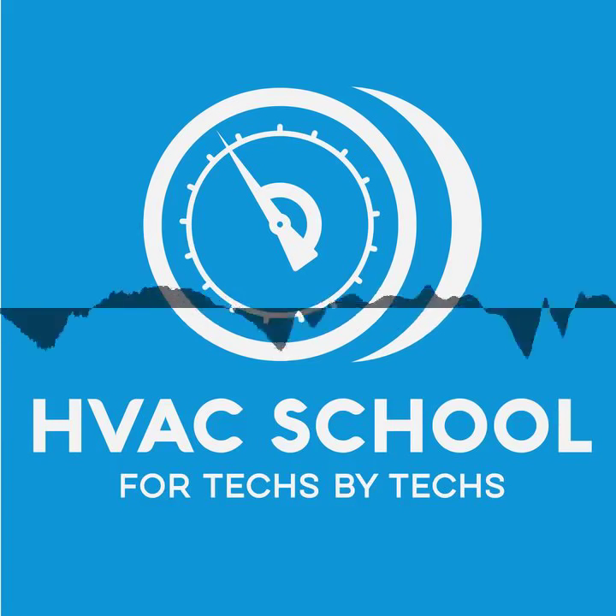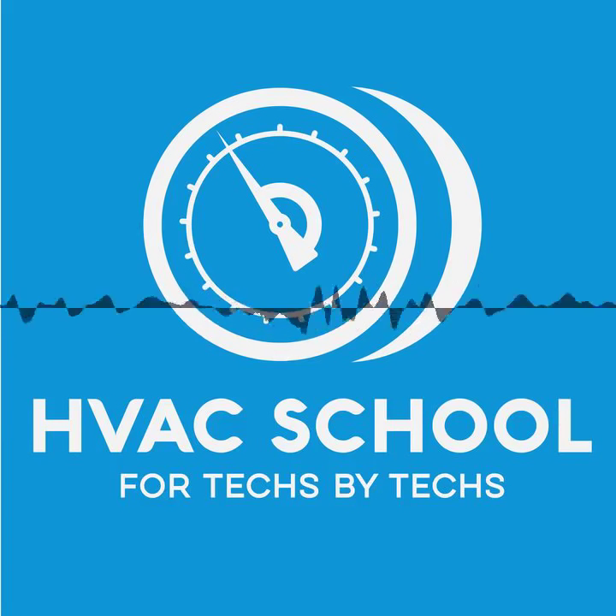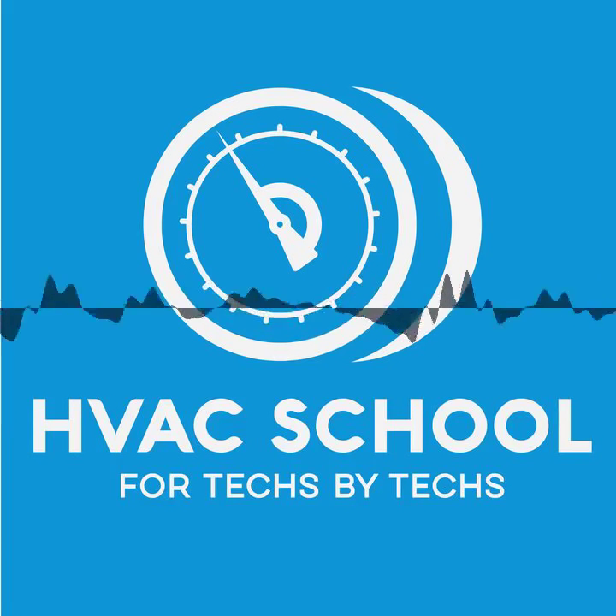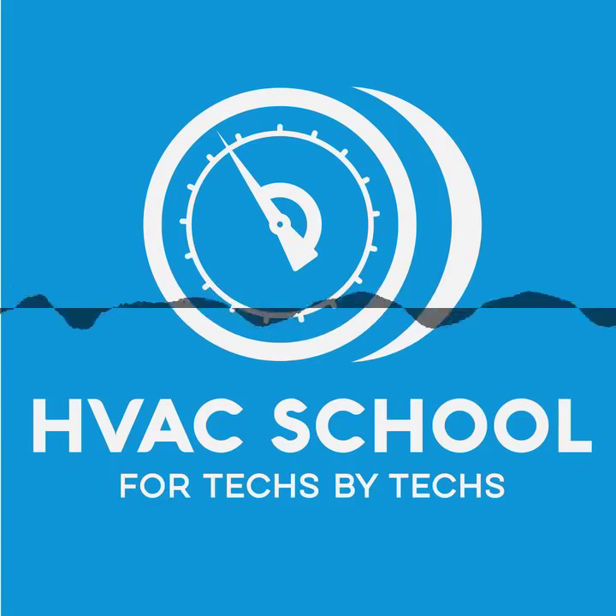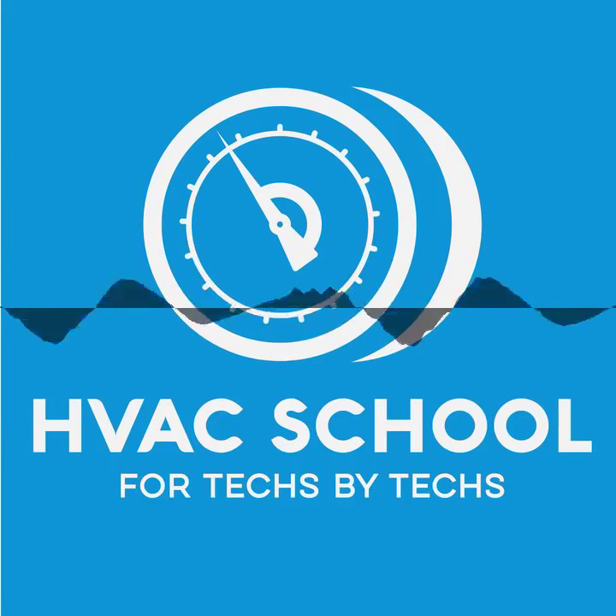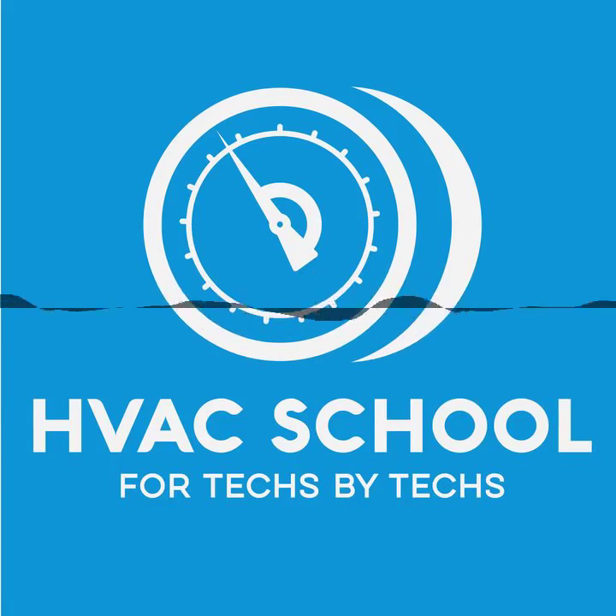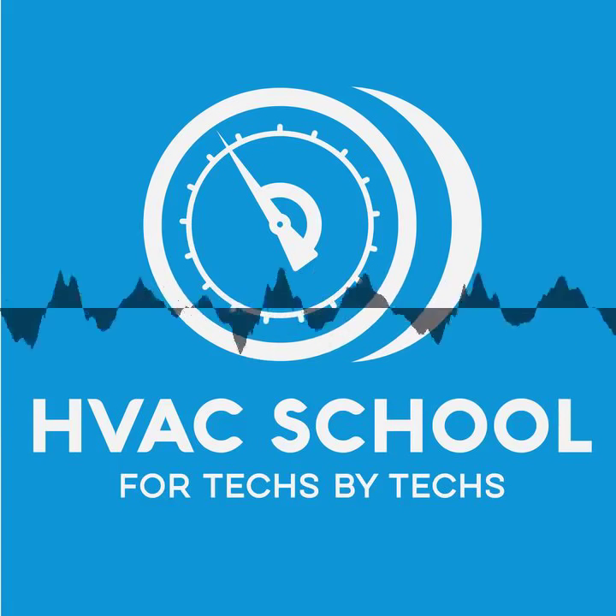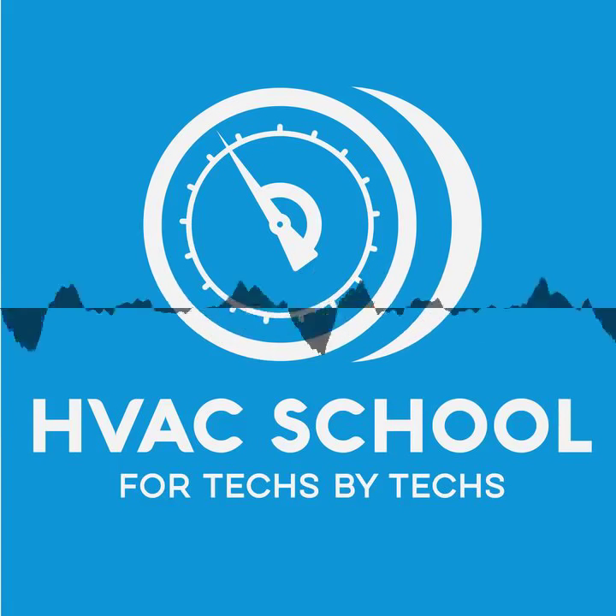All right, so now let's talk about the height, where the copper actually meets that flaring block, where you actually attach it into the block itself. Obviously, it's a little different with the cordless flaring device, but talk about the importance of that height above the block. The thing about R410A is that the molecule is very, very small. And we have to have the right depth of flare or it will not hold the refrigerant inside the system. The height of that flare can actually depend on the type of flare tool that you have.